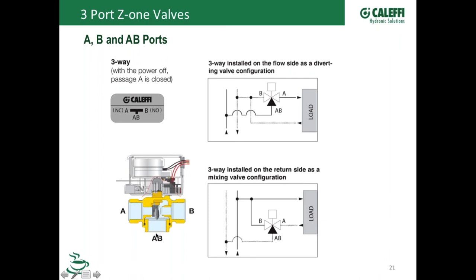Now, we sell this valve for a number of different things, but we actually sell this in a kit for our solar pumping stations. And so basically, the flow comes in here and would go to, let's say, the indirect tank first, the solar tank, to heat up that load. Once that tank gets up to temperature, the valve moves over to this position, and this can go to another load, either another tank or a dump zone or maybe to a radiant zone out in your garage floor or something like that.